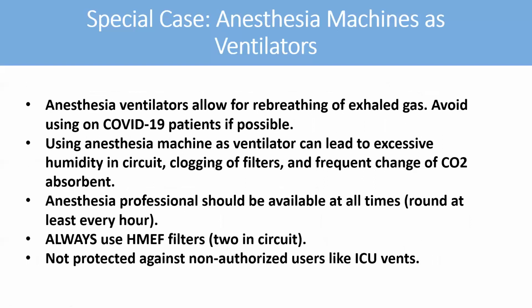So an anesthesia ventilator can basically use a rebreathing, exhaled gas. Avoid using it on a COVID patient, but you can use it on a normal patient as long as you confirm the patient is normal. So no problem. Humidity in the circuit, clogging filters, and frequently changing the CO2 absorber are very important. You need to check all of this every time and practice in a good way. Most of it you can use for non-critical patients. They still need breathing support, but not so complicated.